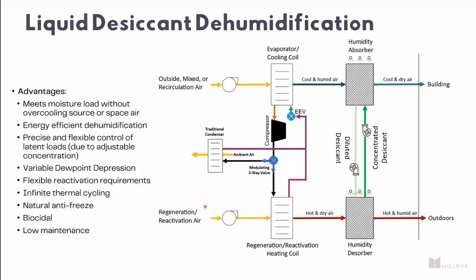This is not connected to the building at all. You're taking outside air in, putting it through a heating coil, evaporating moisture from the desiccant, and then dumping it right back outside. So fundamentally an outside air tunnel, no connection to the building, no cross-contamination with airstreams either. So what's happening here is we're taking outside air in on our process side, passing it through a DX cooling coil. And what's happening is you're cooling and doing partial dehumidification with this cooling coil.